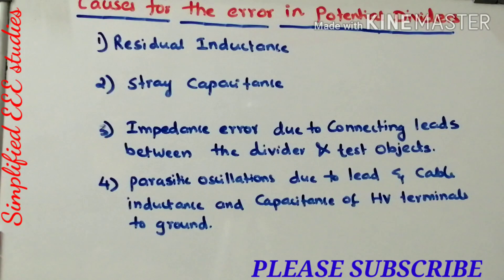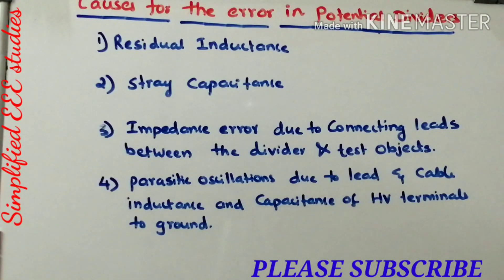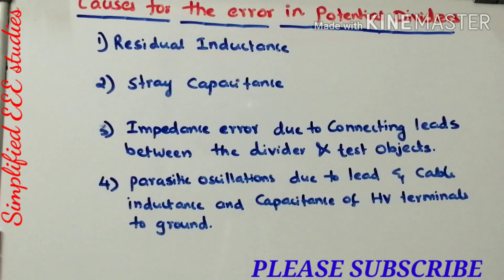The third reason is impedance error due to connecting leads between the divider and the test object. Obviously, you need to connect the low voltage arm to the measurement device, and in between you require connecting leads or wires. The impedance of the connecting leads will cause errors — it may cause a certain voltage drop. That voltage drop among the total voltage should be reduced. Because of the connecting leads, there will be impedance, which results in a voltage drop and you will get a wrong reading.